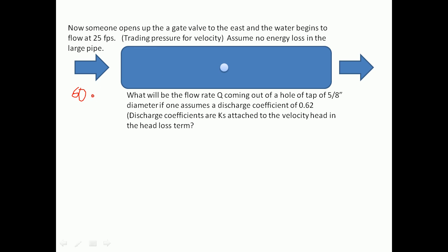Now all of a sudden, that 60 PSI, if you're assuming that there is no additional pumps or anything, in other words you had a static condition, and what happened all of a sudden is someone opened up down here, flowing a flow rate Q, which caused a velocity of 25 feet per second. And what you essentially then have is a trade-off of 60 PSI in just pressure to 60 PSI in pressure and velocity.